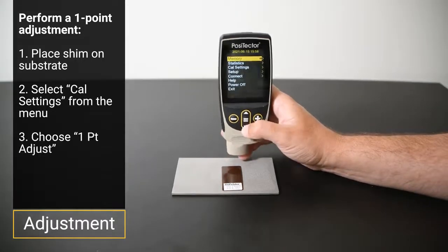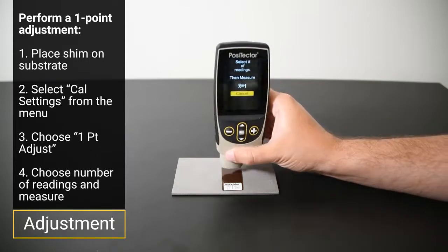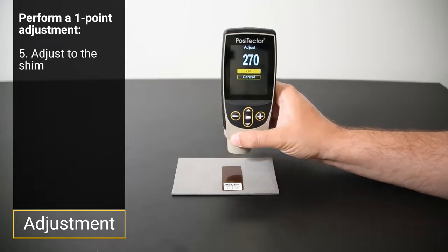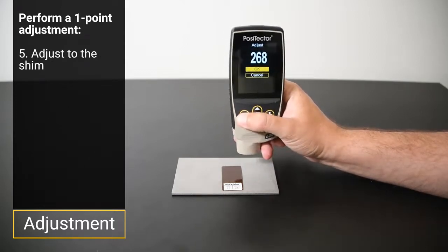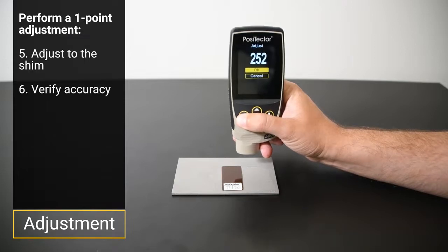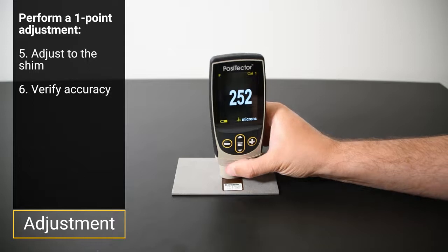Select Cal settings, then one point adjustment. Choose the number of readings and then measure over the shim following the on-screen prompts. The measurement average will be displayed. Use the plus or minus buttons to adjust the thickness of the shim. When completed, verify that the instrument measures within tolerance of the shim thickness.